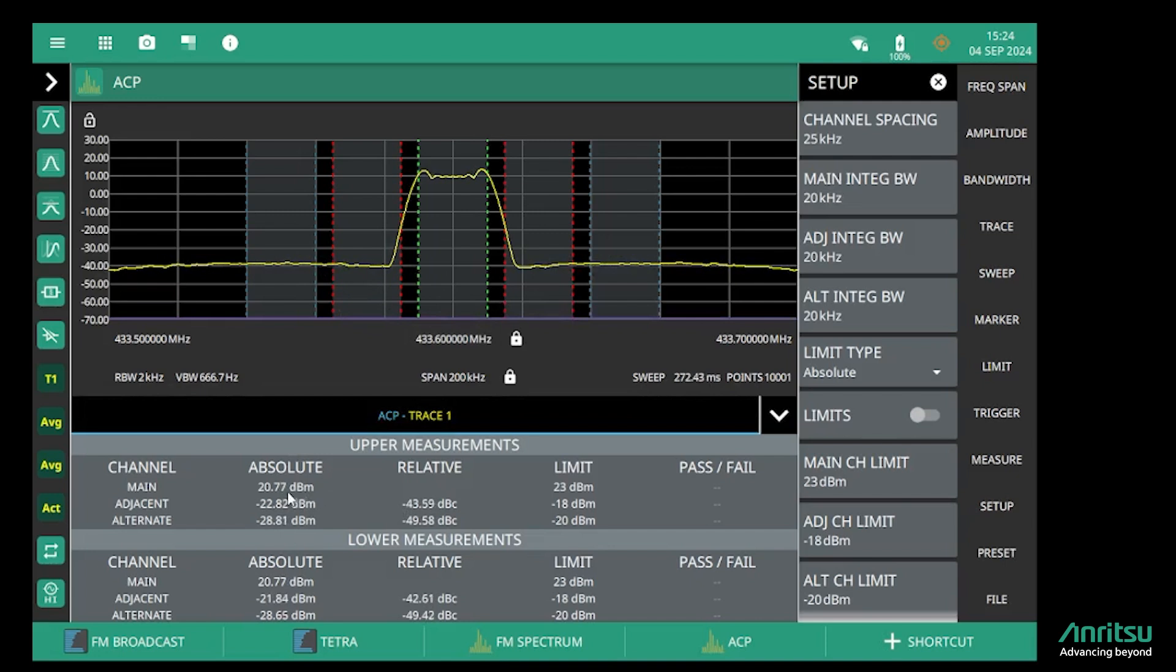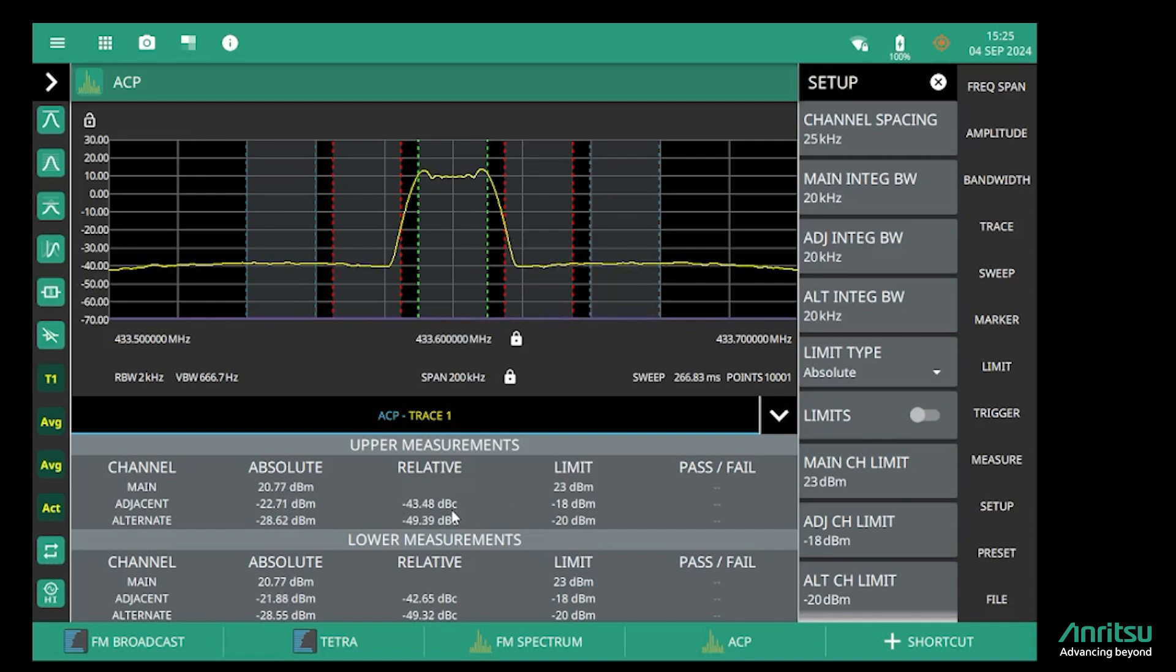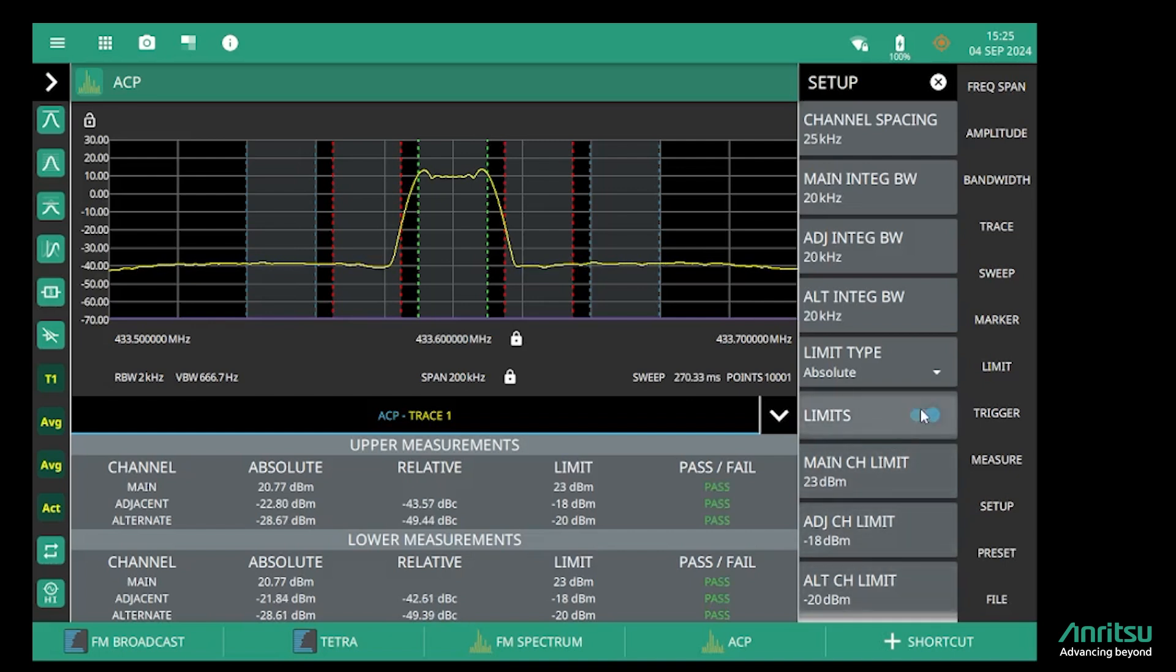So we measure the absolute power of the main channel, and then we measure the relative power of the two lower adjacent channels and the two upper adjacent channels. And again, we can define and apply limits to that to automate the measurement.